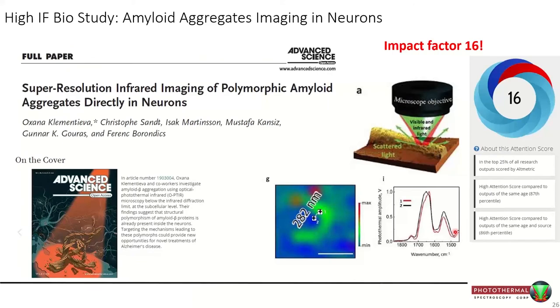Perhaps our biggest publication so far: work with Oxana Klementieva from Lund University, published in Advanced Science, used OPTIR to look for evidence of amyloid polymorphism — and found it. Most exciting to me as an instrument person: on and off a semi-circular feature, two points separated by only 282 nanometers showed clear spectral differences associated with beta-sheet structure in the protein. That's a pretty impressive result for a far-field optical-mode instrument.